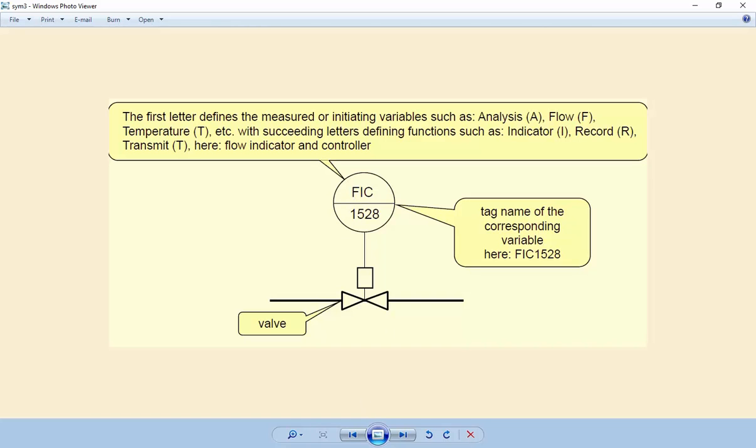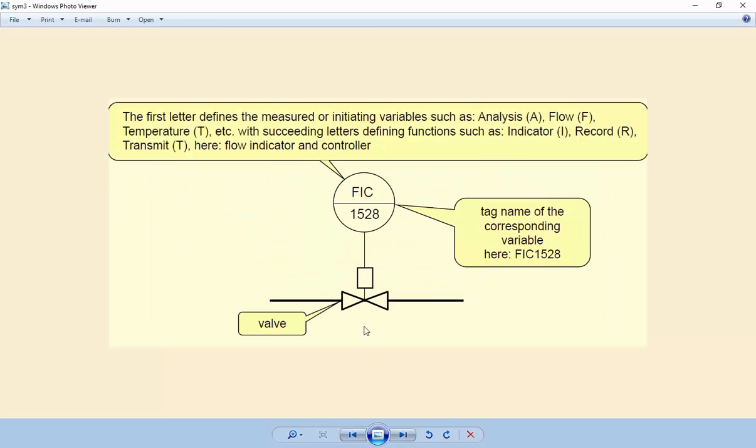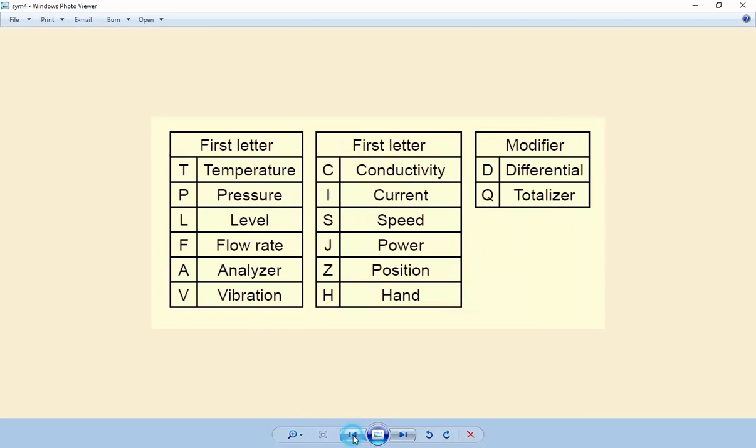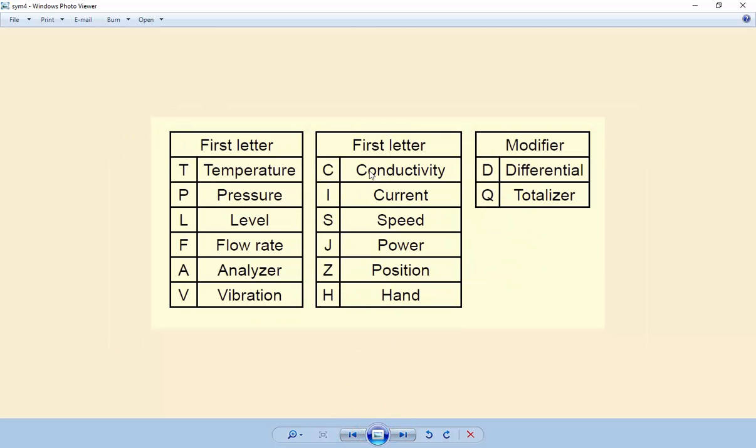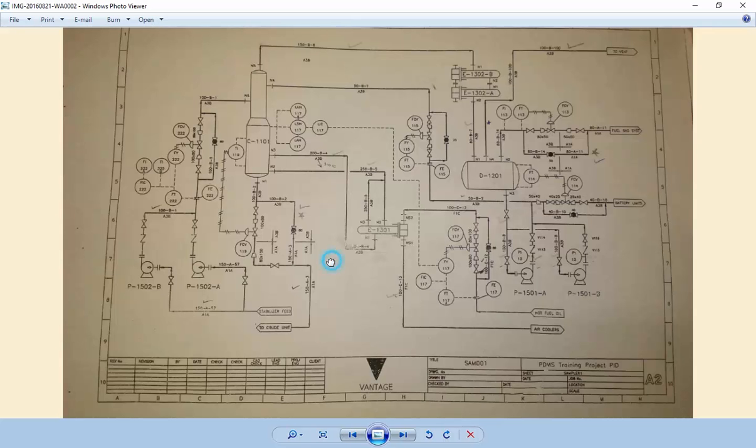Let me clarify the first word. If the first word is F, that means flow rate. If I appears first, it means current. The second word indicates function - I for indicator, C for controller. If C is first, it means conductivity. This is called a tag number or tag name.